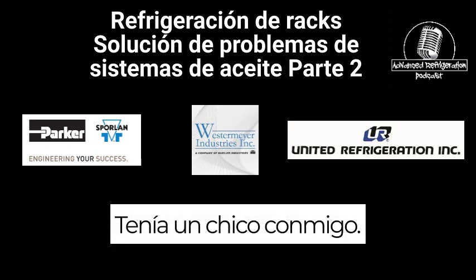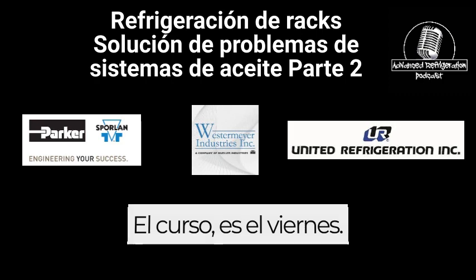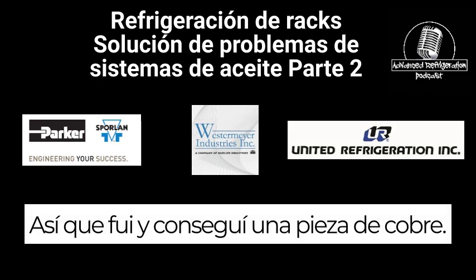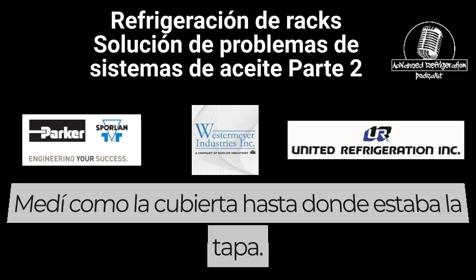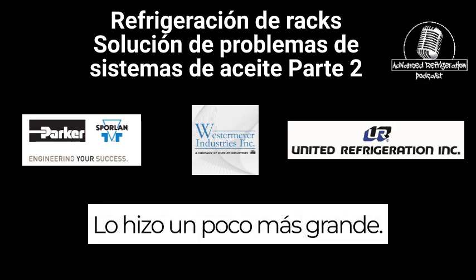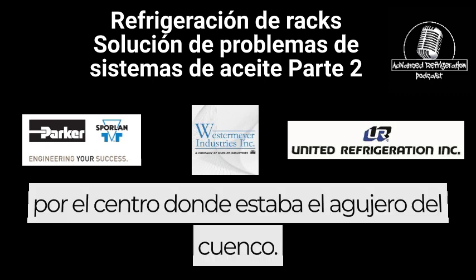I had a guy work with me and he was in the filter, and all I hear was, "Oh," and I went, what does that mean? He's holding the rod in his hands. That went, and of course it's Friday. So I went and got a piece of inch and an eighth copper. I measured the depth down to where the lid was. I made it slightly larger. I took the inch and an eighth copper and I put it down the center where the bolt hole was.